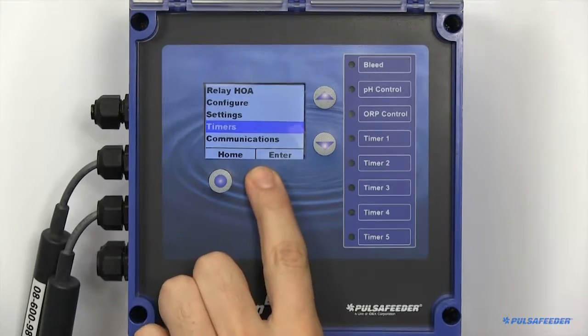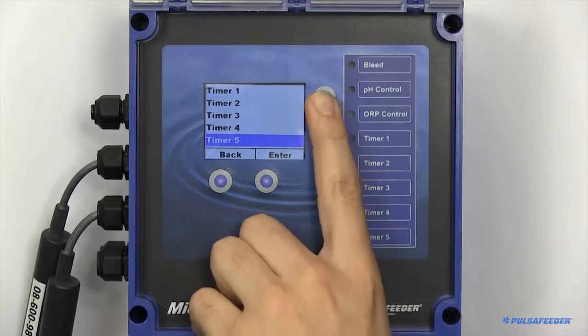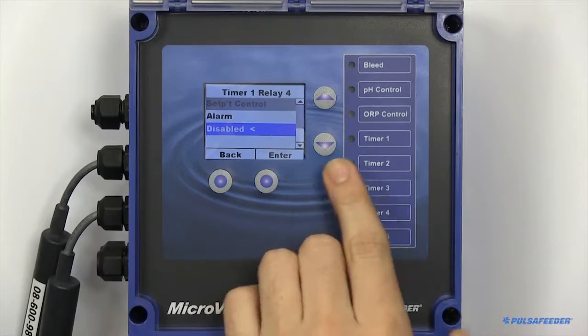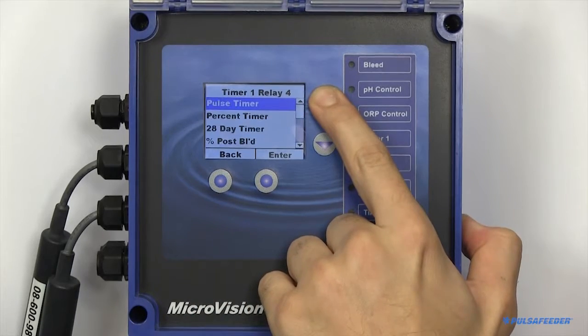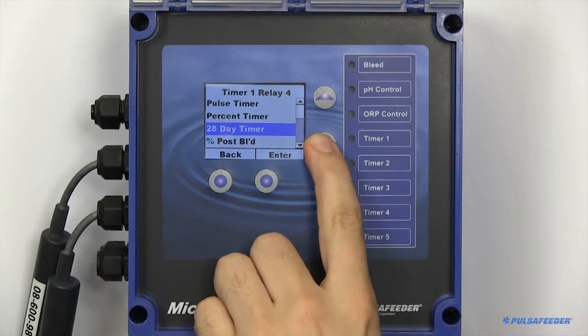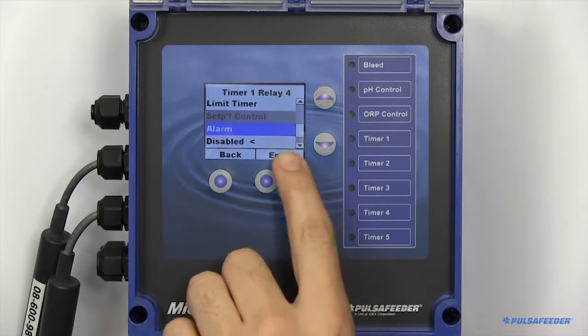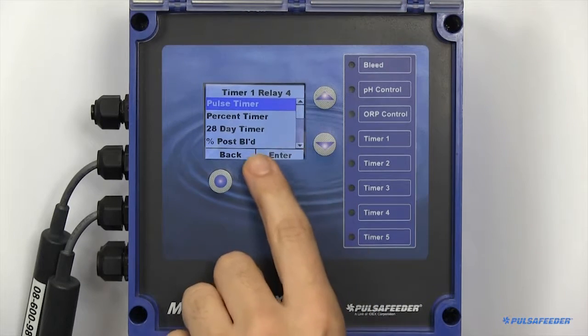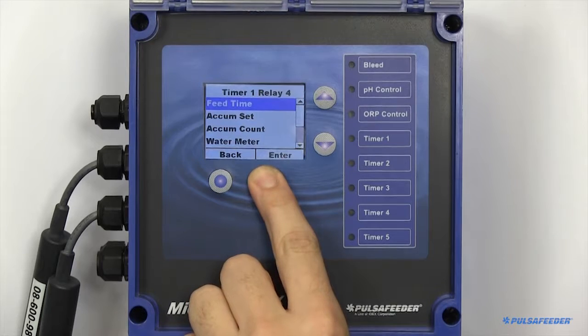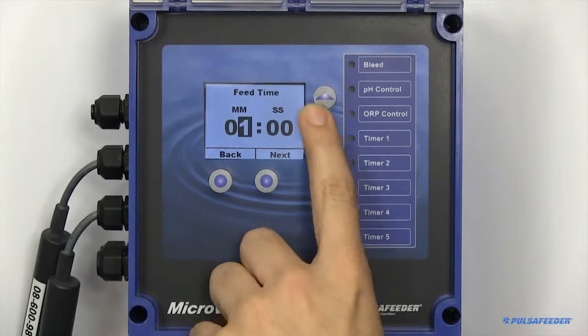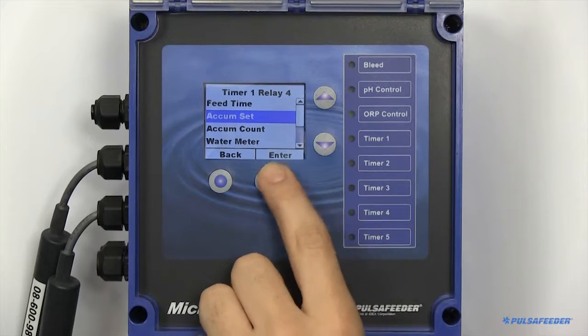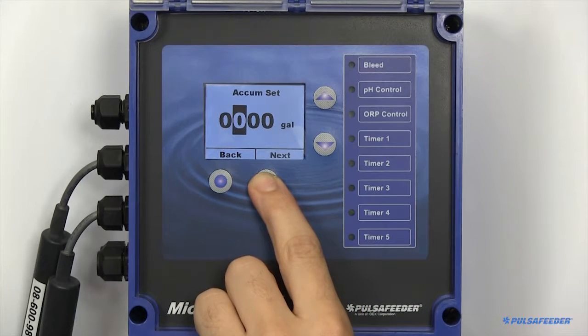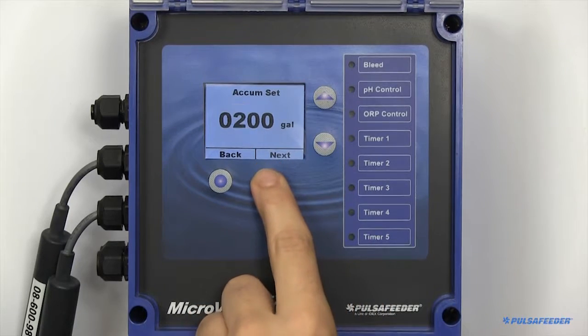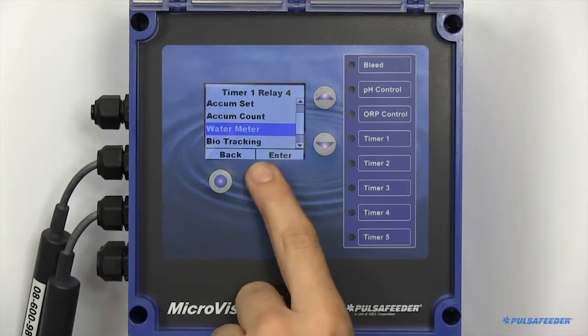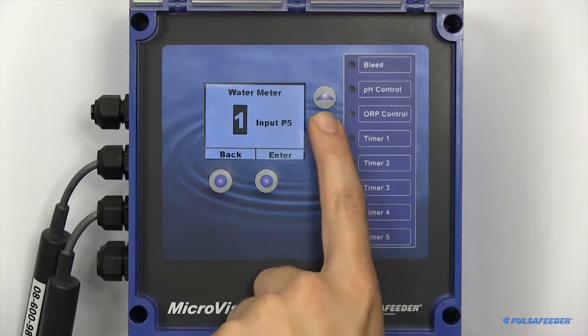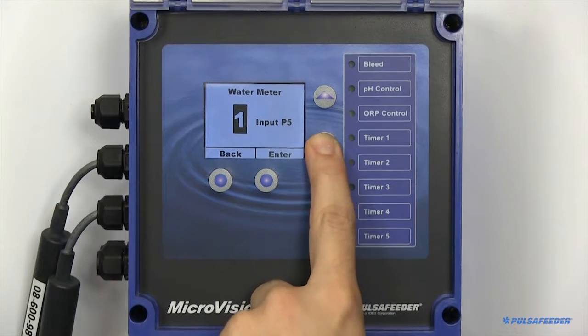The timers page is where you will set up your remaining relays. The relays can be configured as pulse timers, percent timers, 28-day timers or biocides, percent post-bleed, limit timer, or alarms. To set up a pulse timer, you need to configure the feed time, or the desired amount of time you would like the pump to turn on when your accumulator set point has been reached. Set up your accumulator set point. If you have more than one water meter in your unit, you will need to point this pulse timer to the specific water meter you would like to look at.